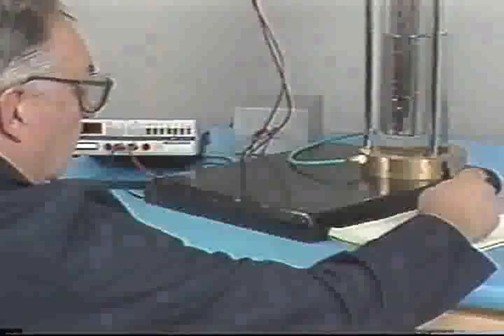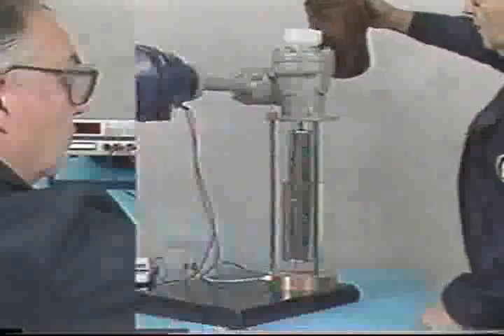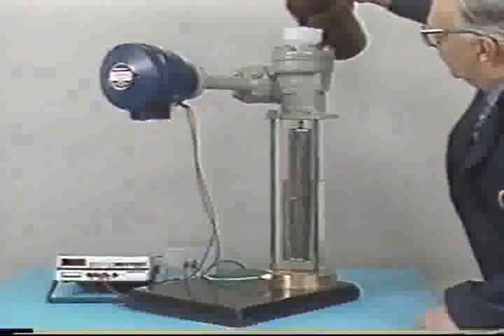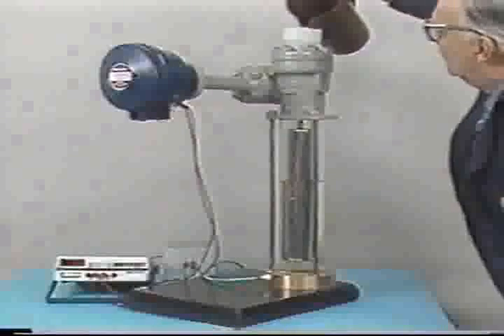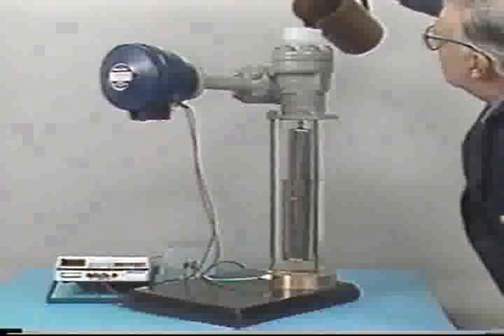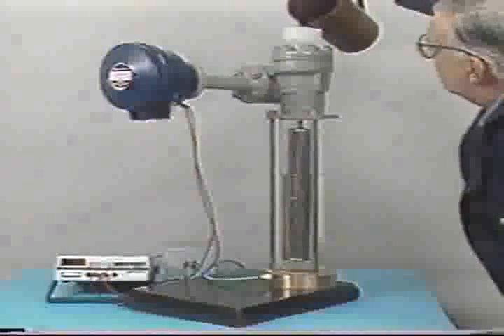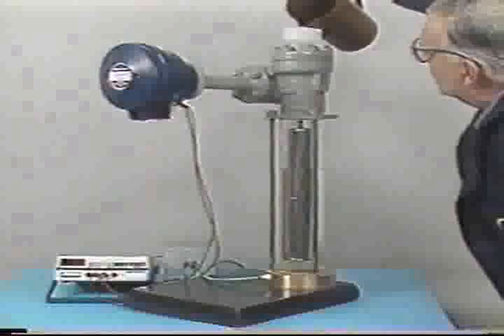Then recheck the zero value by draining the heavy phase and filling with the lighter phase. Make any necessary corrections to zero as you go. When the transmitter produces the expected zero output, drain the lighter phase and fill with the heavy phase to check for span error. Again, make any necessary corrections.